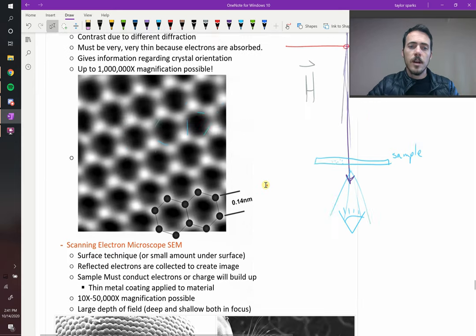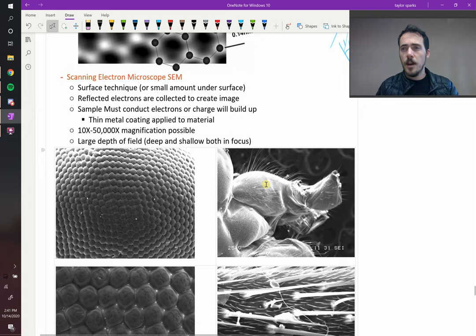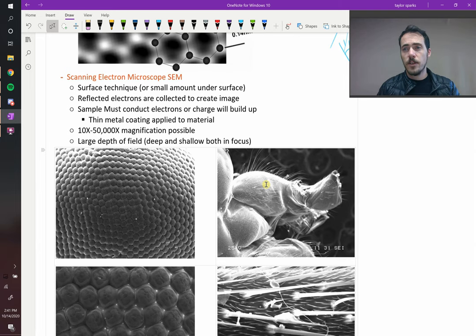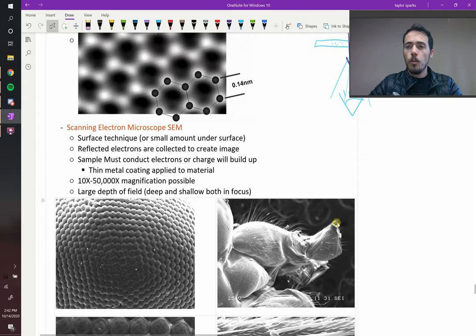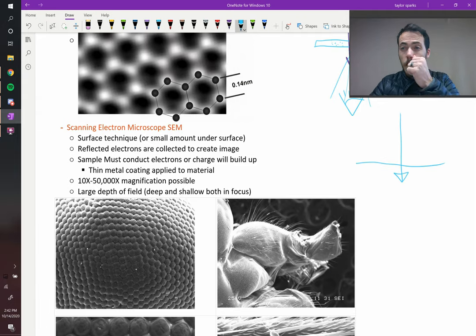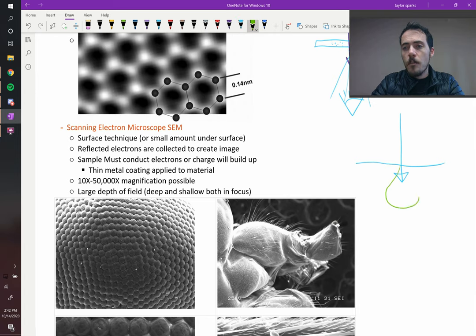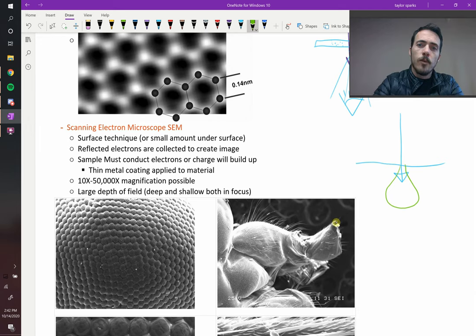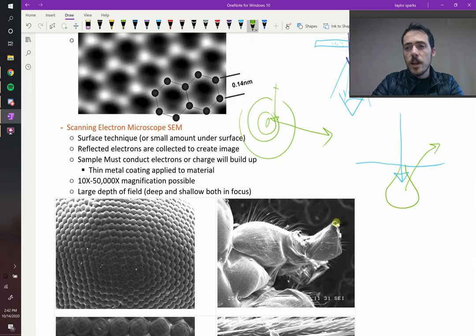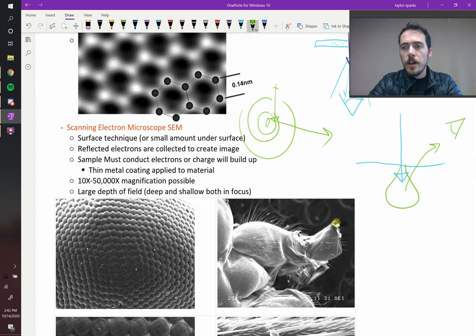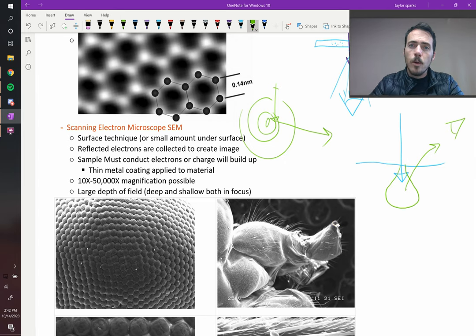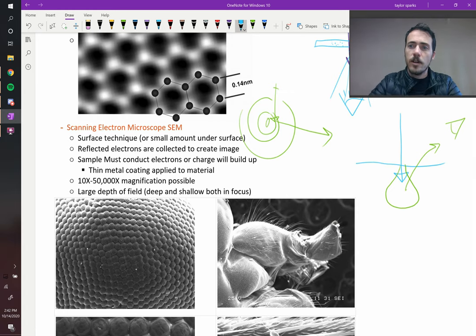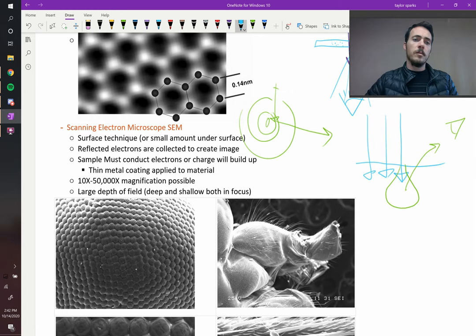So that's TEMs. The other type of electron microscope, which is cheaper, but can't go to quite as high resolution, but is really a workhorse for material scientists is the scanning electron microscope. So it is a surface technique. You're mostly looking at the surface. Technically the beam will interact with your surface. So this is the surface. You've got your beam electrons coming down. They will penetrate the surface a little bit and then they generate within some volume, they're going to generate what are called secondary electrons. So we talked about this before. You've got your atom which has its clouds, and if you knock out this electron, it goes flying out. Those are the electrons that come flying out. These secondary electrons. And then you've got a detector over here that basically catches those things. So how do you create images with this process? Well, you move the beam. You're able to raster it. You're able to scan it. Using that electric and magnetic field, you're able to move this thing and raster it. So you can move your beam over to here, move it to there. You can move it in two dimensions and you can create a really great image.